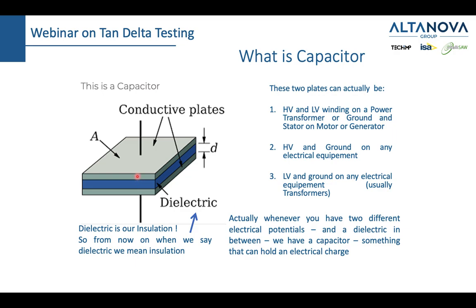Or maybe it's not the high and low voltage side of the transformer, maybe it's high voltage and ground, or maybe low voltage and ground on some of the primary equipment. So whenever we have two different electrical potentials and a dielectric in between, we have a capacitor, something that can hold an electrical charge. Even an overhead line running above us has a parasitic capacitance between that line and the ground. Of course, it's a very small capacitance because the distance is very big, but it's there. And since it's there, let us use that to understand the state of our insulation.